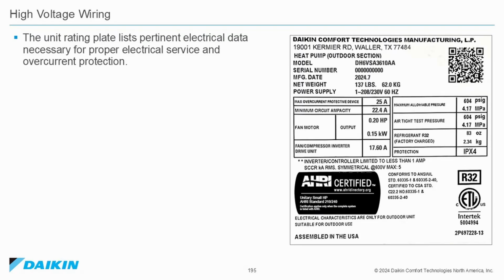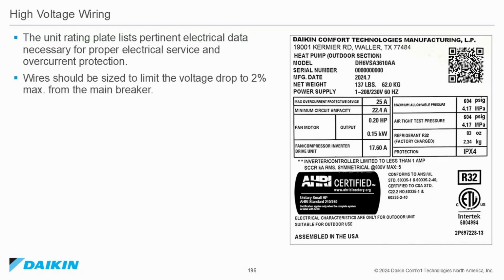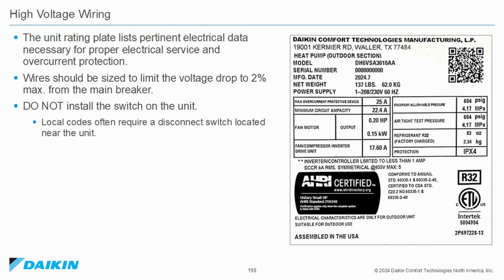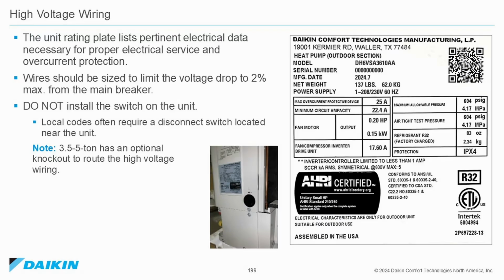High voltage wiring. The unit rating plate lists pertinent electrical data necessary for proper electrical service and overcurrent protection. Wires should be sized to limit the voltage drop to 2% maximum from the main breaker. Do not install the switch on the unit. Local codes often require a disconnect switch be located near the unit. 3.5 to 5 tons have an optional knockout to route the high voltage wiring.